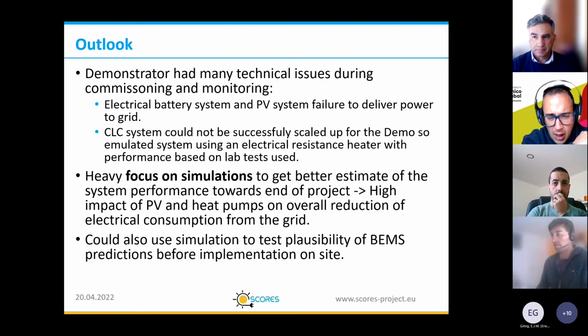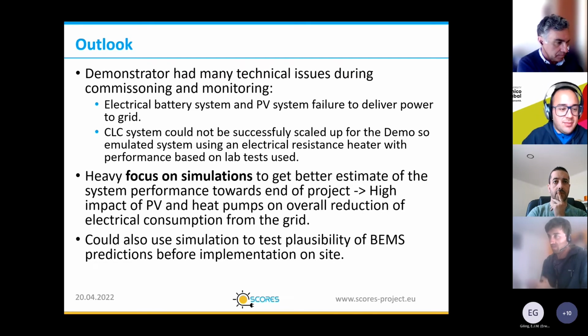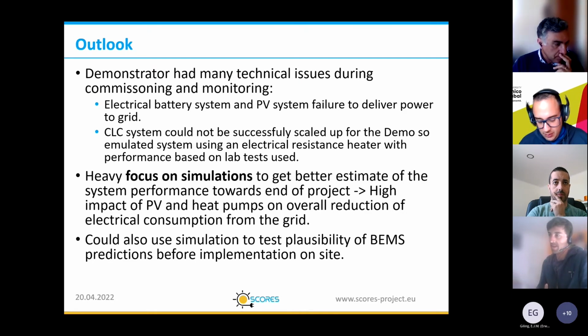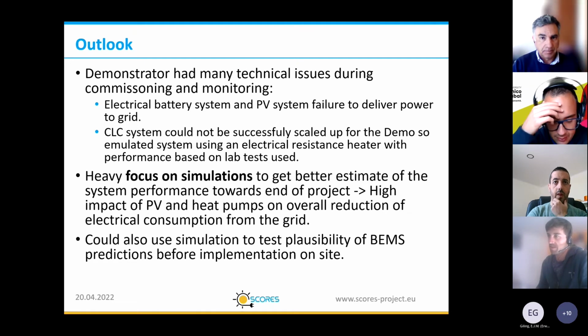We also used this model to test simulated variables against monitoring data. For small windows of monitoring data where we collected weather data, we fed this identical weather data into the simulation models to observe the validity of individual subsystems, comparing the COP of our heat pump systems to what was observed in the field, and also predictions of how space heating might look over a certain time period from the BEMS.